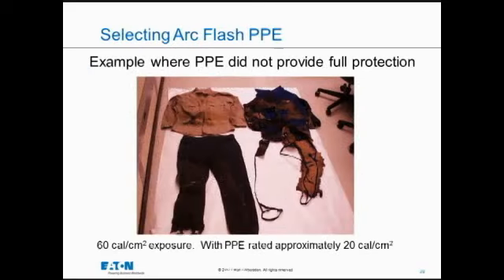This picture is just showing the after effects. This is taken on an office floor, a picture of 2 layers of clothing that protected an employee pretty well, not completely, but the big news here was this person more or less walked away from the incident. Their clothing did not catch on fire and continue to burn. It was arc-rated clothing. There was more of a hazard than what the clothing was capable of handling.